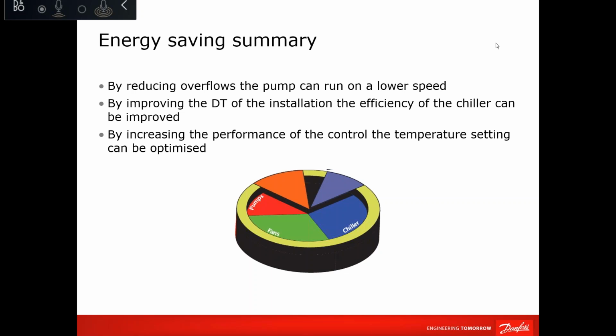Let's say you have an existing project with DRVs and two-way valves, and you decide to change partially, or one phase, and you will put in PICV within the same loop. PICV will have the minimum required differential pressure to give you the design flow, while the DRV was balanced based on the overall system pressure. You might need to visit the DRV, but for the PICV you don't need to do anything except the setting before installing the valve. Did that answer the question?